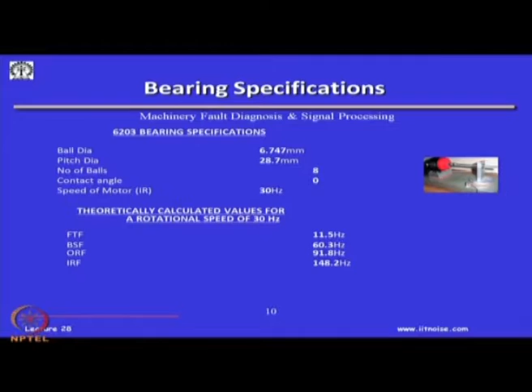The theoretically calculated values for a rotational speed of 30 hertz: the fundamental train frequency is 11.5 hertz, ball spin frequency is 60.3, outer race frequency is 91.8, inner race is 148.2. You will see here that nowhere are the bearing frequencies multiples of 30 hertz. They are decimal fractions of the rotational speed, so that is a good indicator.